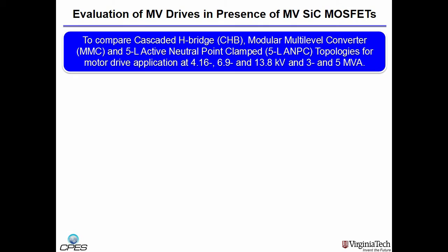Finally, having the test results, we compared the cascaded H-bridge, modular multi-level converter, and 5-level active neutral point clamped topologies for industrial motor drives at 4.16, 6.9, and 13.8 kilovolts, and 3 and 5 megavolt amps. We selected so many voltage and power levels so that we could find the breaking points for each topology or semiconductor technology.